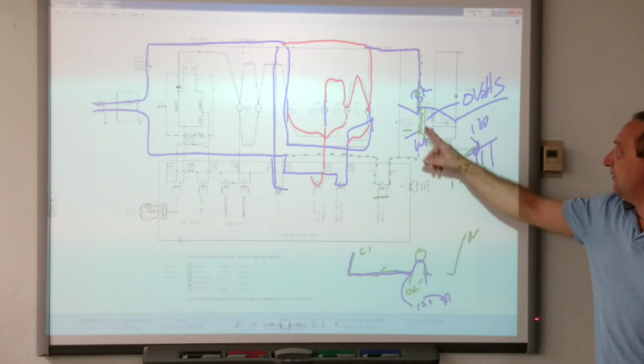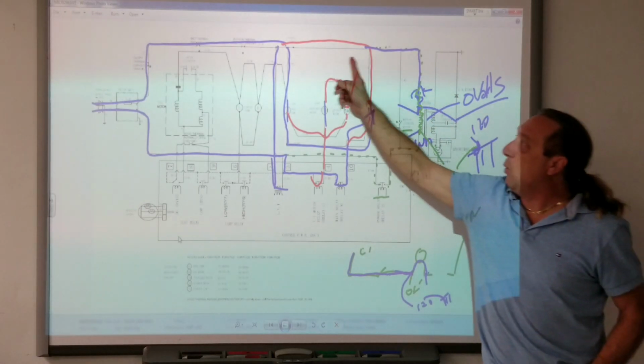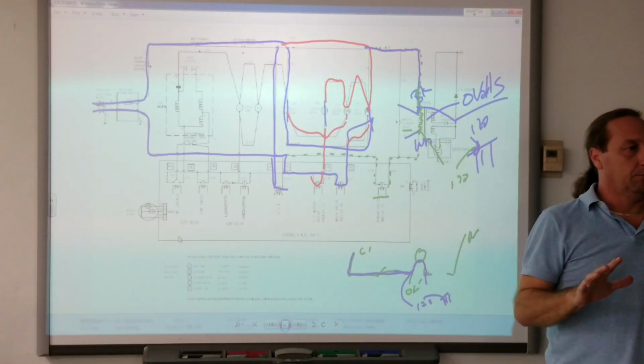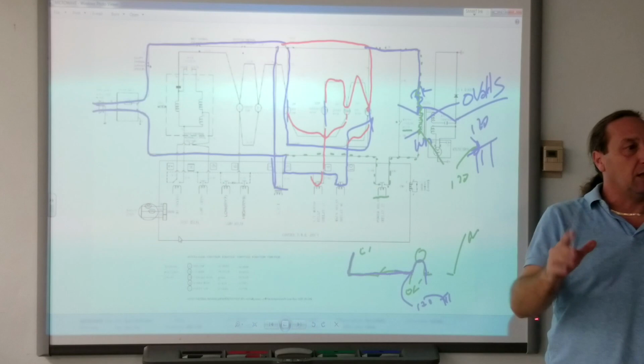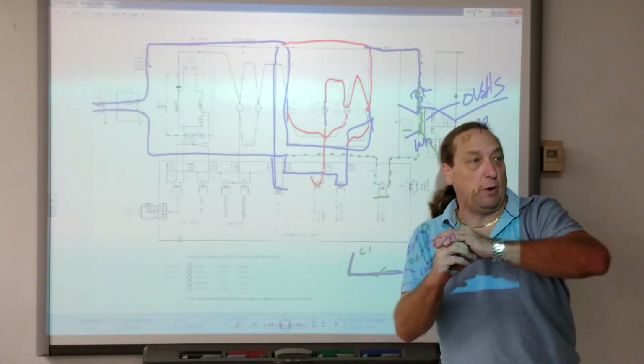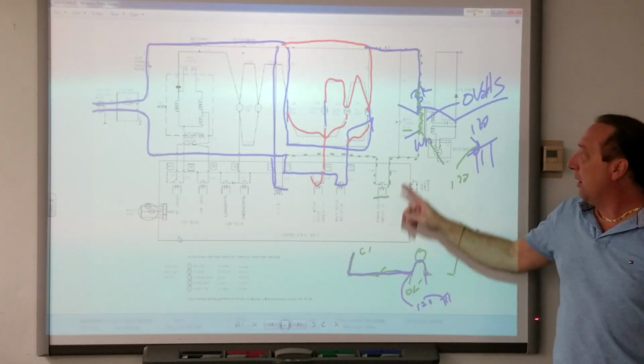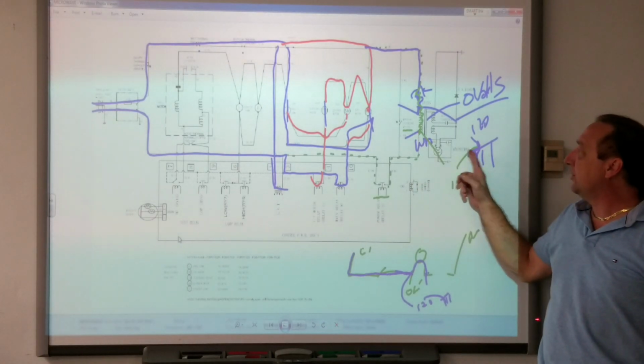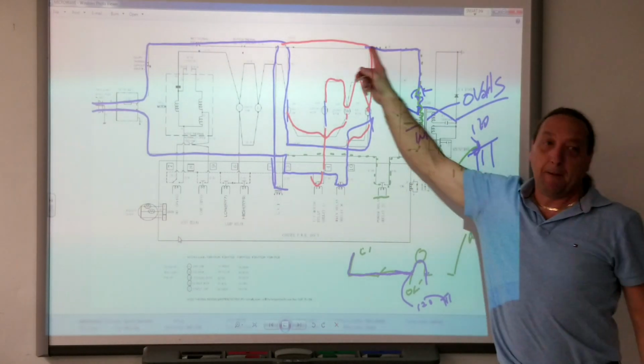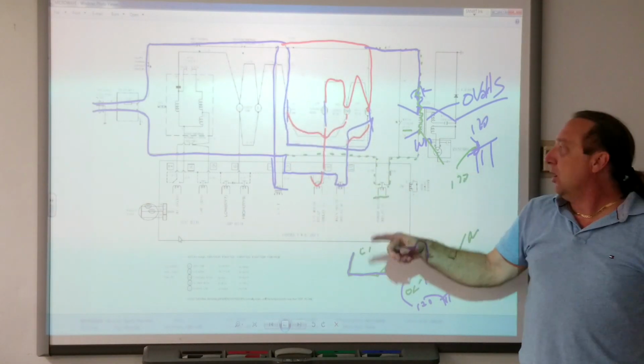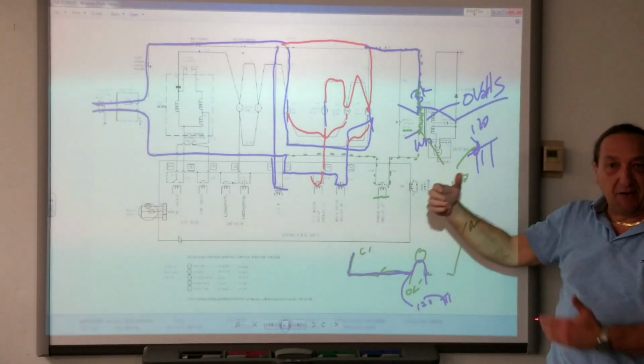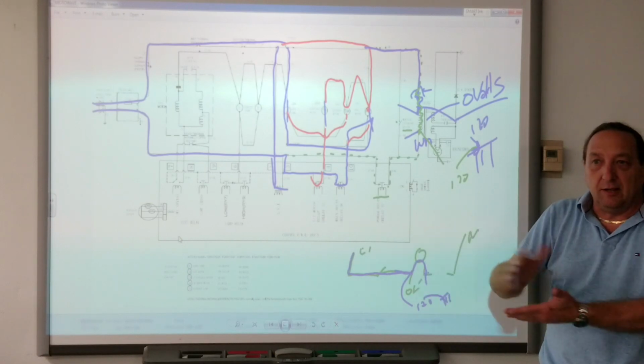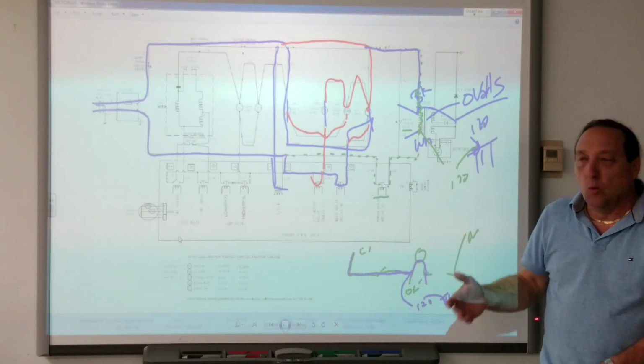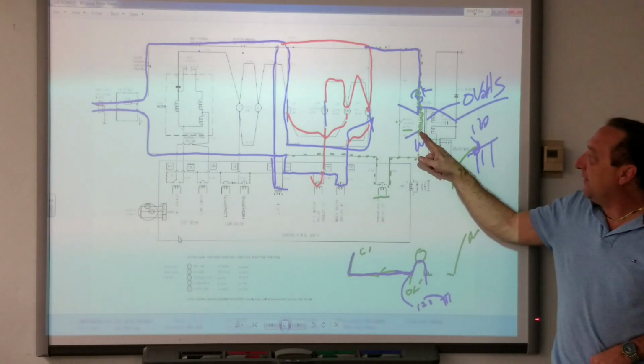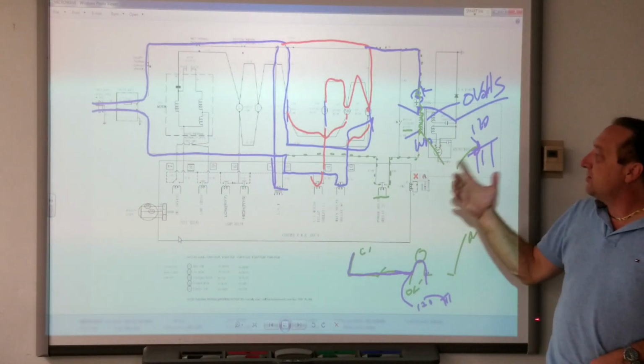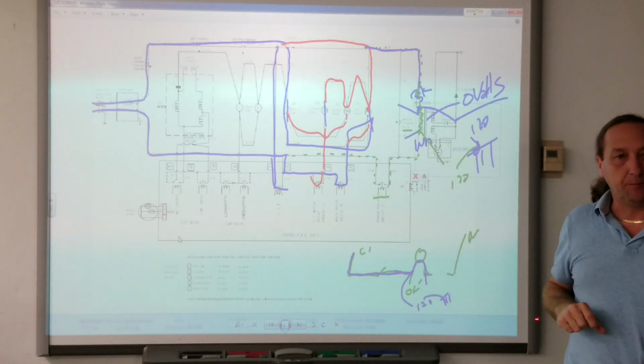There's no way I'm going to get a voltage reading from here to here if one thing there is bad. So when I'm doing a voltage test, I'm checking everything in that circuit right back to the plug. When I went from here and had voltage to ground, it's because I went through here back. Now, if I find voltage here, I have to keep going till I lose it to find out where it's lost. Where would my next test be if I tested from here to ground and had it? Where's the next test going to be after that?